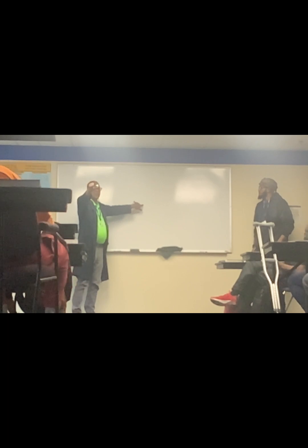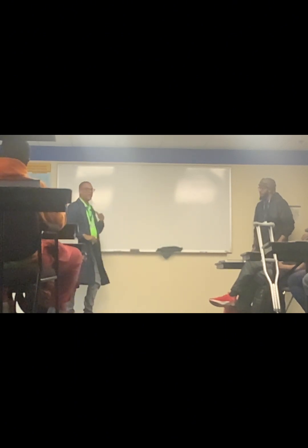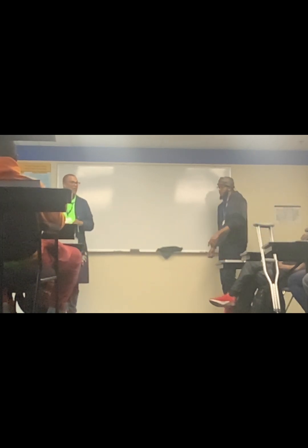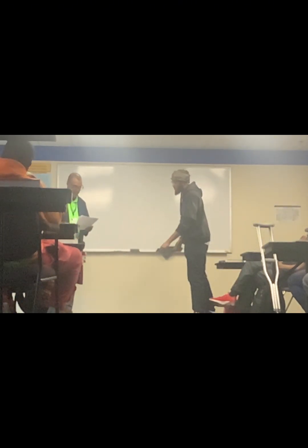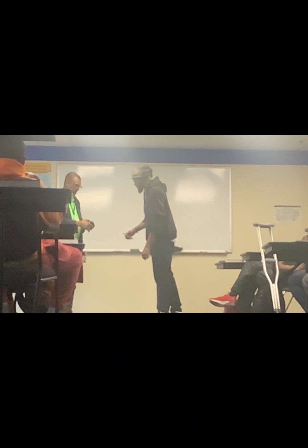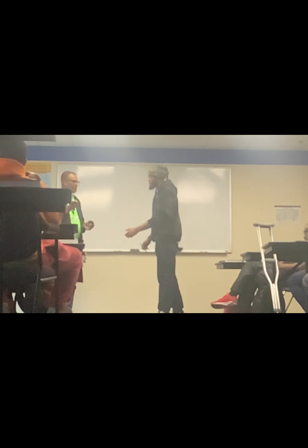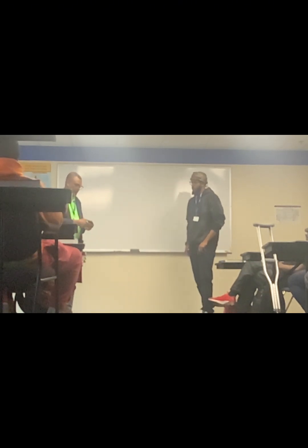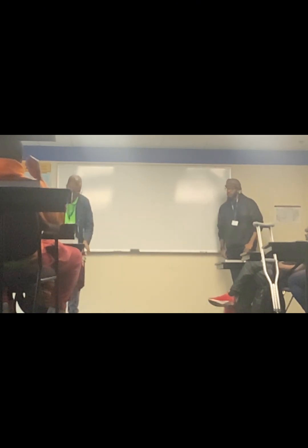And so that way, if I have 240 here, all that's telling me is I'm good from the circuit breaker, because I got my 240. But if the machine didn't run when the coil closed on 24 volts, I could go here to ground, I'm good. Here to ground, I'm not. I don't have enough voltage to run the machine. Where's that on one of these? L1 and L2? L1 and L2 is here and here. So you do one L1 and then the ground. Yep. But the ground's gonna be on the front. It could be a case ground, put it on the metal of the machine, and it should read 120. And we'll do it in the lab one day.